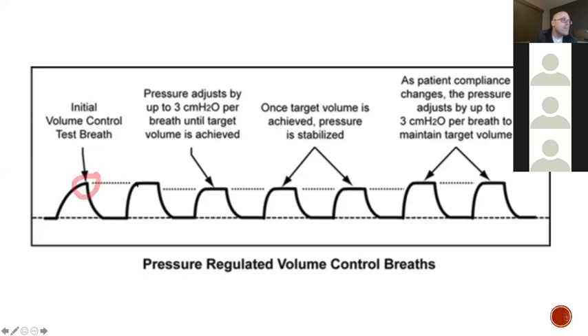So then the next breath is a pressure breath. You can tell it's a pressure breath because it comes up, stays up, and then falls down. So this pressure breath went to whatever amount of pressure it was that the volume took on the first breath. And then it will adjust the pressure. So you can see this one is a little bit lower, and it got back the right amount of volume. So then this next one, same. The next one, about the right amount of volume, same. Then it says, oh, I got back a low volume, so I'm going to give a bigger amount of pressure to give a bigger breath. So you can see it's adjusting itself as it goes along.